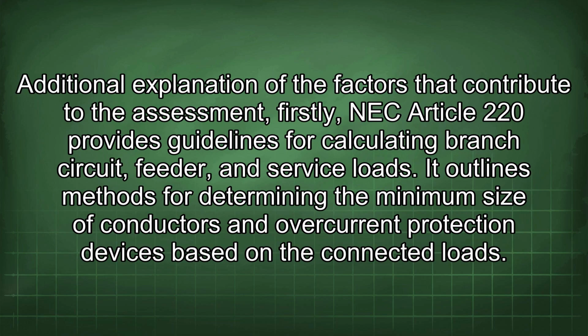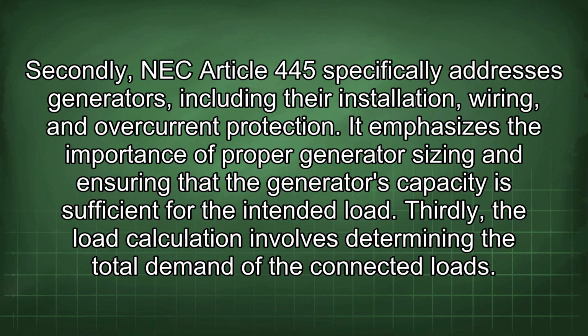Additional explanation of the factors that contribute to the assessment. Firstly, NEC Article 220 provides guidelines for calculating branch circuit, feeder, and service loads. It outlines methods for determining the minimum size of conductors and overcurrent protection devices based on the connected loads. Secondly, NEC Article 445 specifically addresses generators, including their installation, wiring, and overcurrent protection. It emphasizes the importance of proper generator sizing and ensuring that the generator's capacity is sufficient for the intended load.